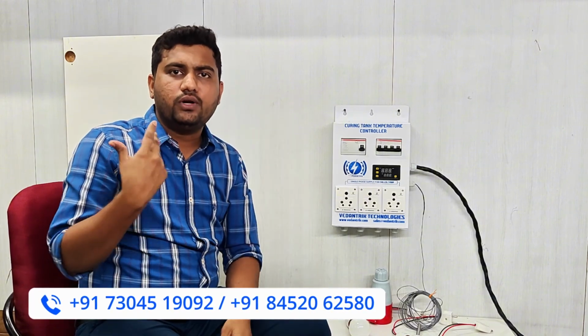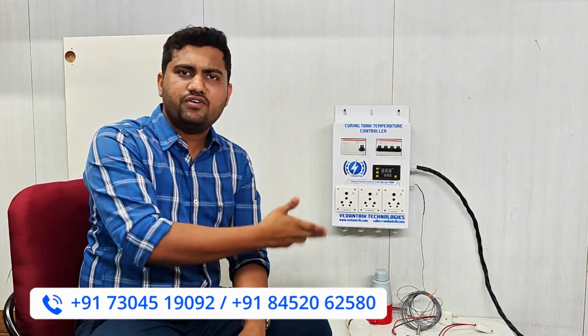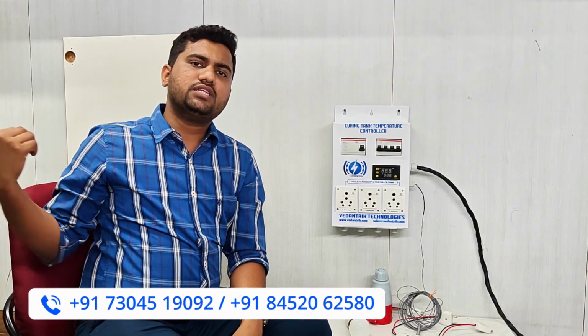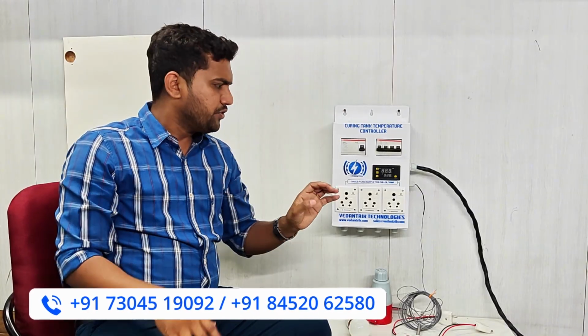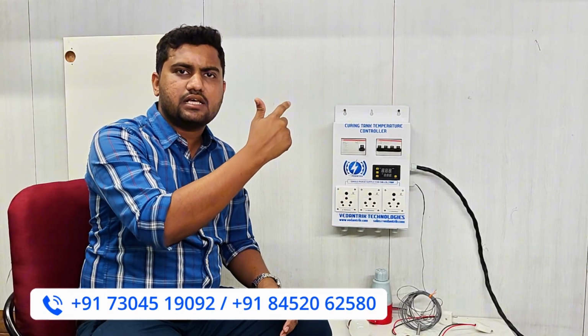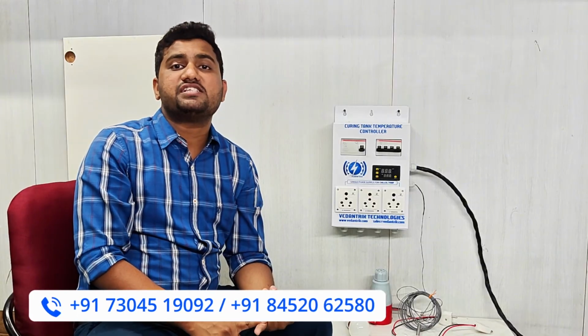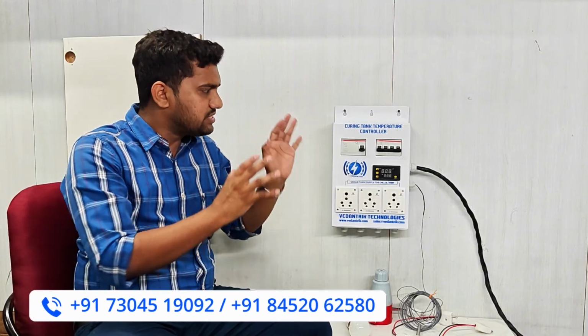Suppose you do not want to circulate the water; then all 3 sockets are available for the chiller. The same way you connected the heater to all the tanks, you can connect a chiller in all these 3 sockets, and the chiller water can be circulated with this particular tank. So that's how, using this single curing tank temperature controller model, you can use a single phase heater, a 3-phase heater, run your single phase pump for water circulation, and connect a single phase chiller to these sockets. So your single controller is capable of doing all the operations.